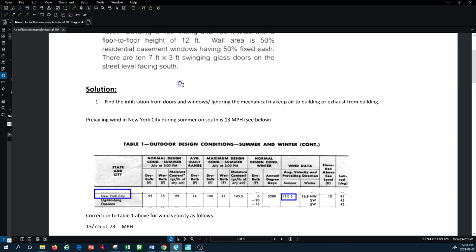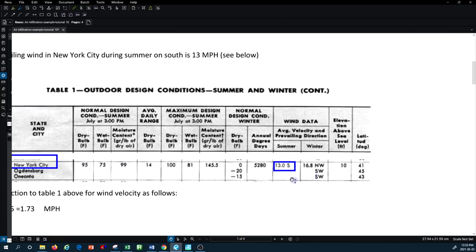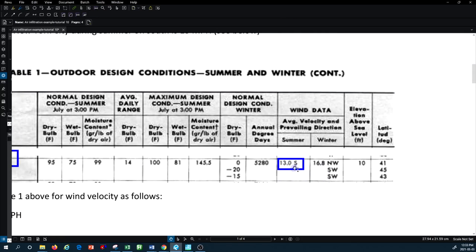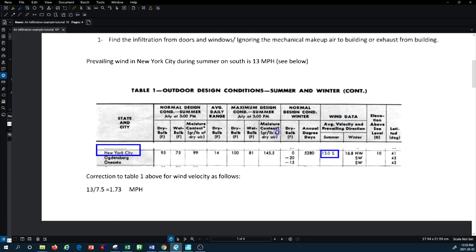From the ASHRAE standard, you need to find the outdoor design condition for summer and winter. There is a table where you look up New York City to find the wind data — the prevailing average velocity and prevailing direction. The prevailing wind direction is south, with a wind velocity of 13 miles per hour. This is historical data available in the ASHRAE standard.